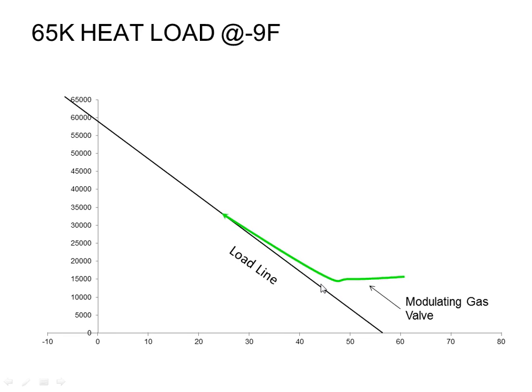However, whenever it's below 48 degrees, this guy is going to start ramping his gas valve open and closed to match the gas capacity to whatever the house needs. When it's below 48 degrees at this guy's house, his furnace is never going to shut off. It is going to run the entire winter long. Now that probably sounds like a bad thing if you said that to most homeowners. So if you just went ahead and gave them this furnace and installed it, and then they saw their furnace running all the time, they would probably freak out after about 2 weeks, and they'd call you and say, "Hey Ryan, this furnace you put in, it never shuts off.